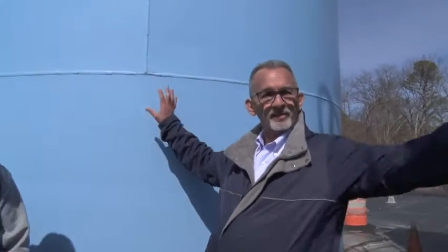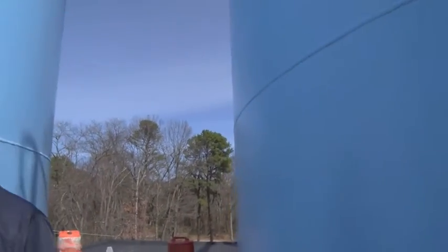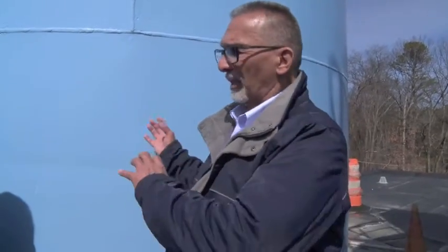These are the lime silos. Each one holds about 20 tons of lime. And like I said before, the lime is added to the water just to increase the pH of the water. The groundwater pH is very low. We have different wells over here, and the different wells have different pH. So we have to watch and see which water we're using in which clarifier so we can adjust the pH accordingly. Okay, we're going to go see the clarifiers.